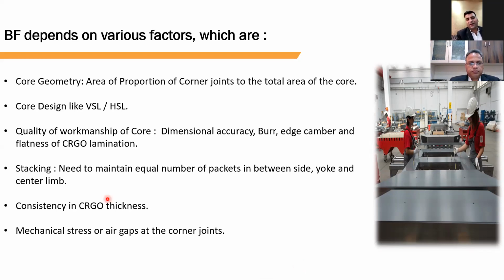Another thing is burr level. If you are not using carbide cutters, and not setting the slitting machine properly—maintaining the proper gap between cutters as per the formula—you cannot minimize the burr. The ideal burr should be less than 10 microns; if it is more, that adds to the building factor and deteriorates the core's performance. Burr is the extra thickness at the edge of the CRGO, and it applies not just to the slit edge but also to the cutting edge, guide holes, and V-notch area.